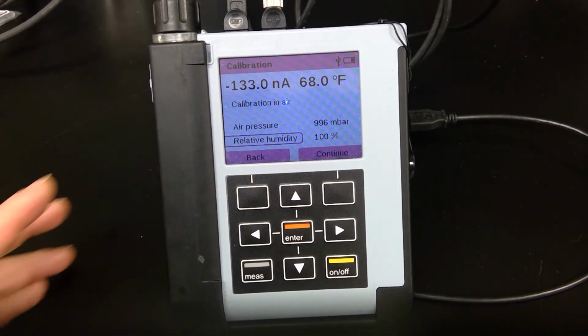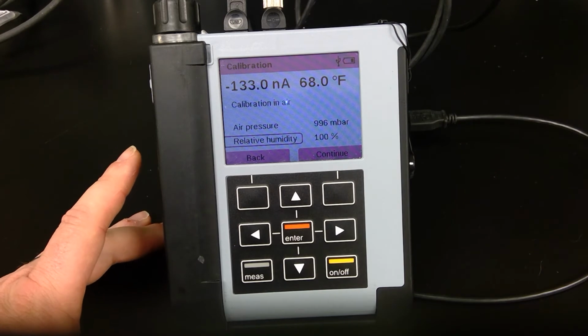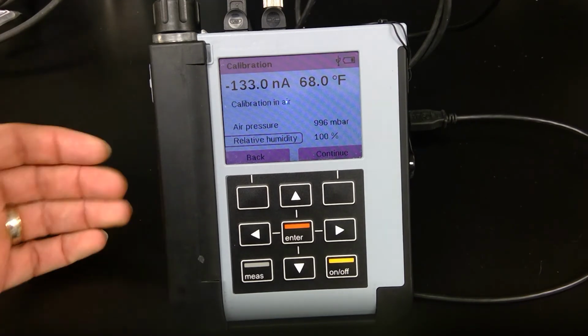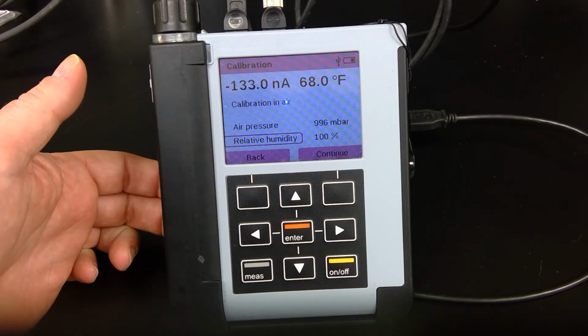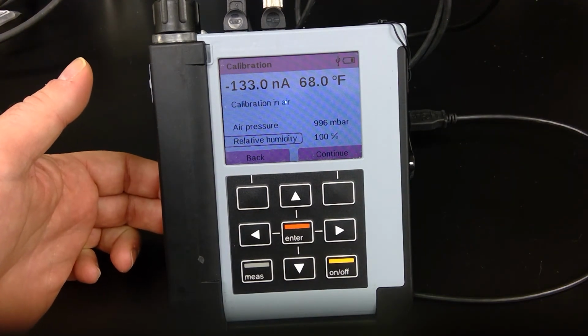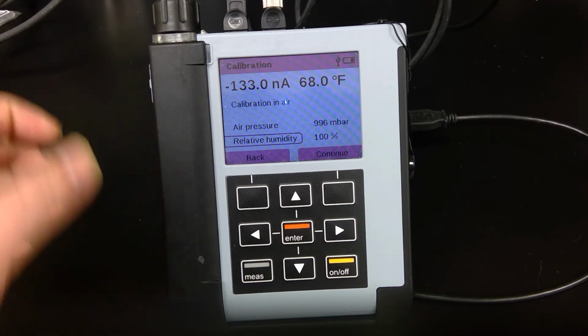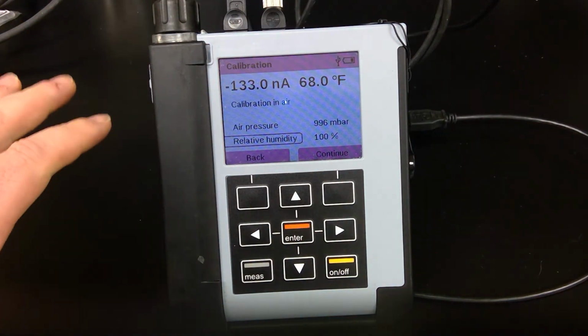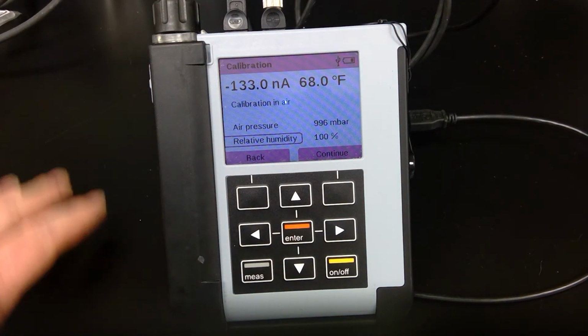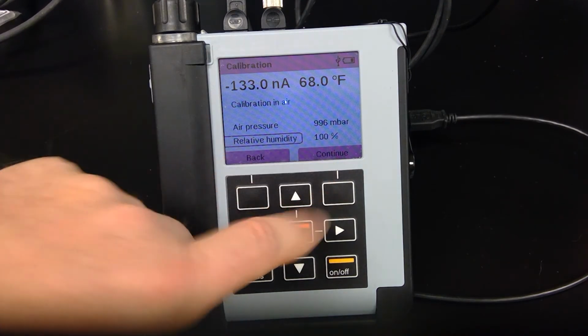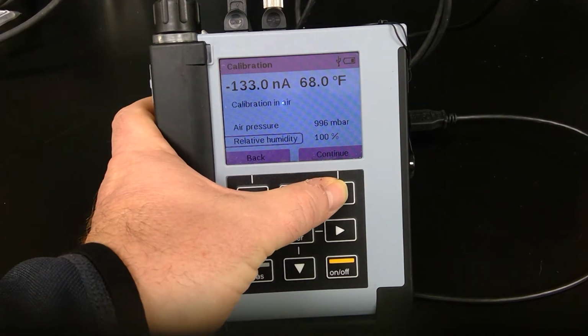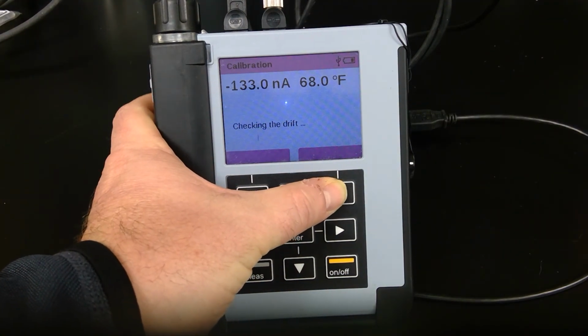Now, keep in mind, when you're using a Portavo and you have the system set up for air pressure, there's a small air pressure device on the back of the Portavo that's monitoring the real air pressure. So you do not have to touch this for this type of calibration. So leave it at 100% humidity, or change it to 100% if it wasn't already there, and you hit continue.